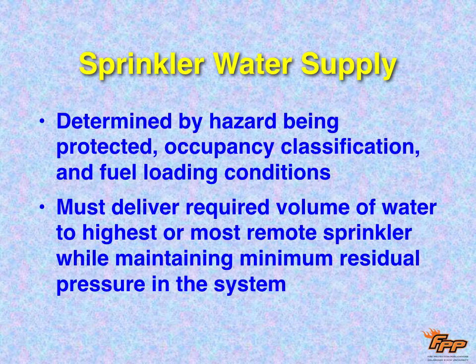Now, with our sprinkler systems, they're going to be added based on the hazards that it's protecting. So inspectors will look at the code, and the code tells us that the occupancy classification and the kind of fuel load, or the stuff that'll burn in the building, is going to determine whether we have to have a sprinkler system. Once we determine that you have to have it, then we have to figure out how much fire load, fuel load, there is, and based on that, how many BTUs that is going to put out, and then how many BTUs could be in the building. That's how much water is needed to put the fire out.